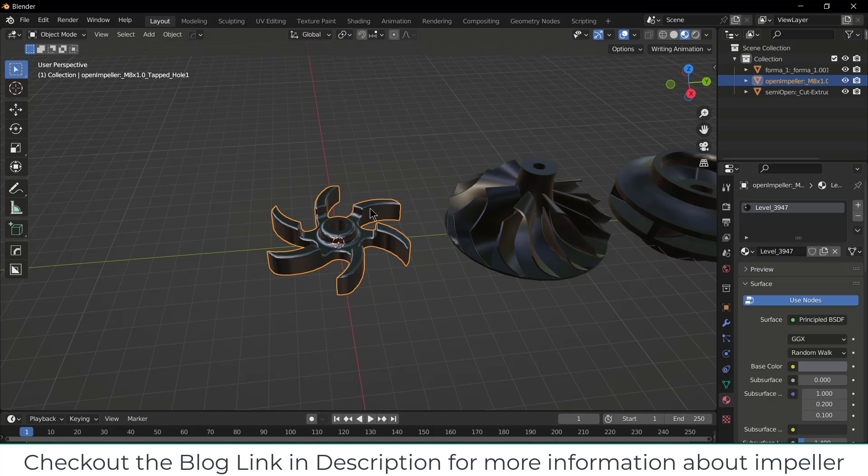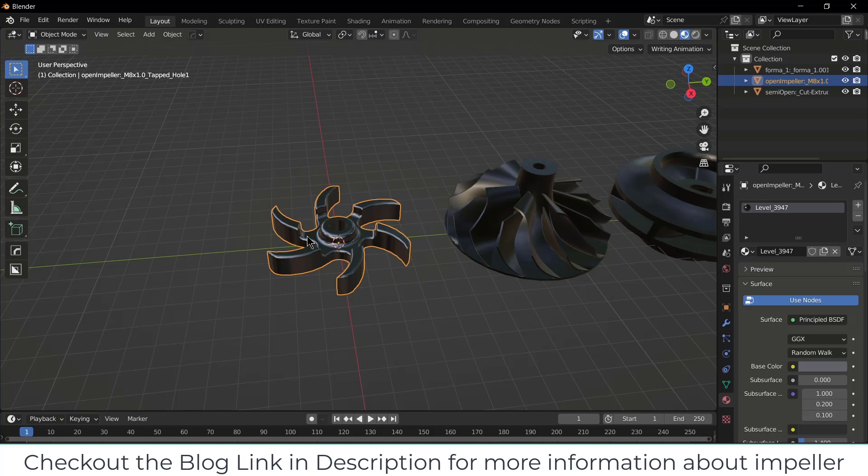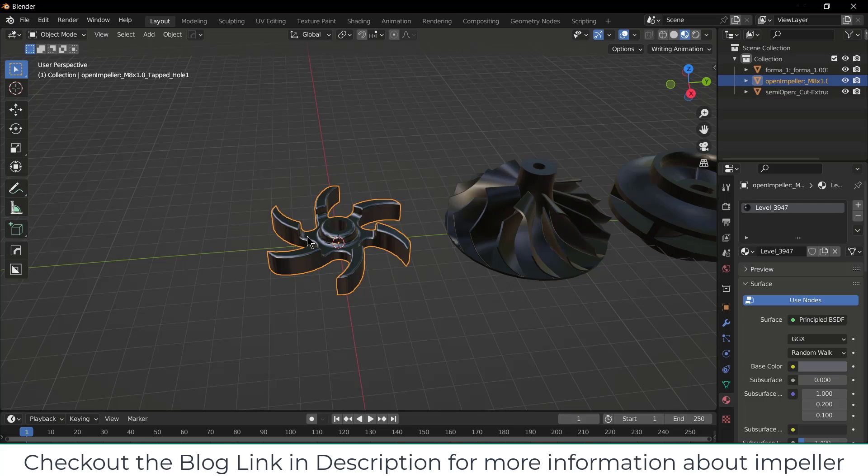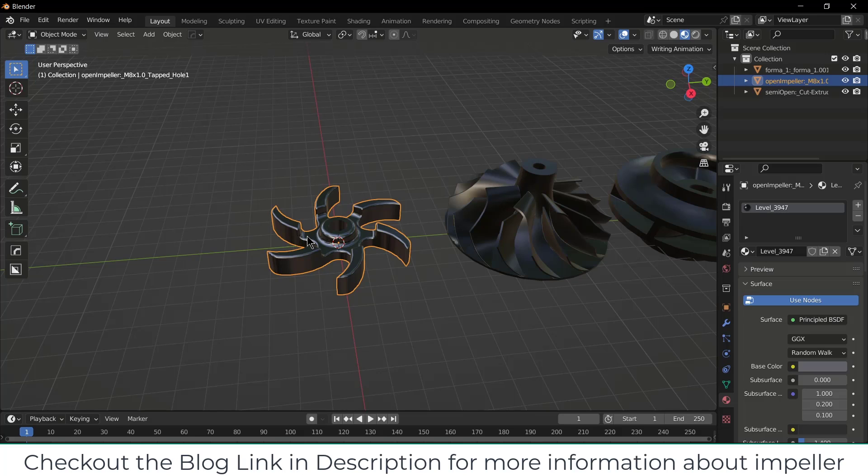What are its disadvantages? It is good, no doubt, but it's only good for small workload. For example, if you want high volume capacity or workload, then open impeller is not a good choice for you. It has very low efficiency, so not a good choice for high power requirements. And its net positive suction head is reduced due to cavitation effect. Cavitation is an effect where bubbles generate and damage the plate. I will cover a special video on cavitation and how that works.